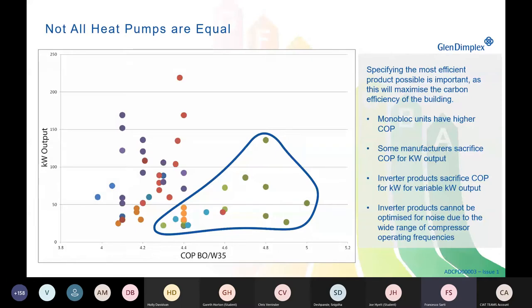So other than the SCOP, of course, you're going to select your heat pump based upon the output. In this graph, we can see the output of the heat pump, so its capacity, against the COP at specific conditions. B0 means brine at 0 degrees, and W35 is water at 35 degrees.